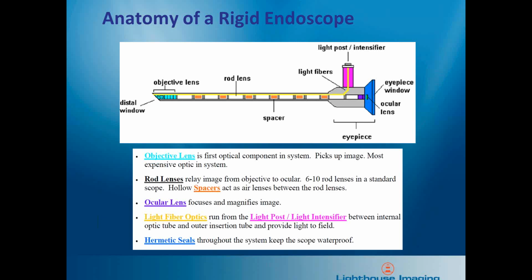At the same time, going in the opposite direction of flow would be the illumination bundle fibers wrapped around, typically speaking, the lens system. So the construction of rigid endoscopes most commonly is kind of a tube inside of a tube inside of a tube. The inner tube being the optics, a middle tube being the illumination fiber bundle, and then the outer tube being the sheath that we interact with.